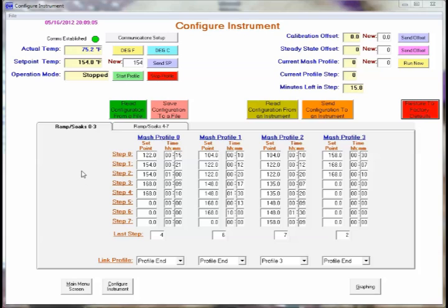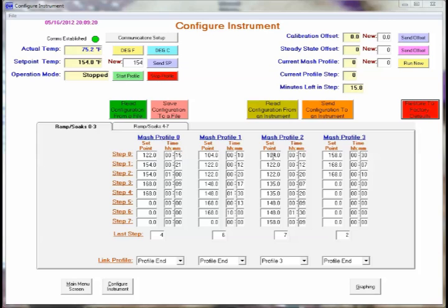Now we'll talk a bit about the MASH profile setup. For each MASH profile we have up to eight steps, steps zero through seven. And the unit comes equipped or set for a few sample programs that you can use for a default.